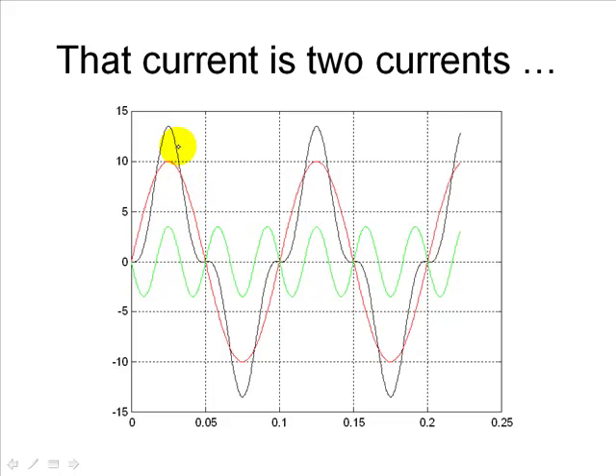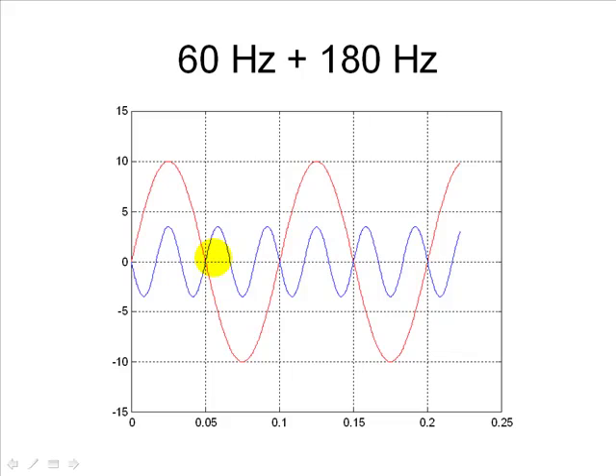We say the magnetization current actually is the sum of two sinusoidal currents. One that is a 60 Hz current, the red one, the fundamental frequency one. And another one, the green one, that is oscillating three times as fast as the fundamental one. We call this a triple frequency current magnetization. And these are the two components of that magnetization current.